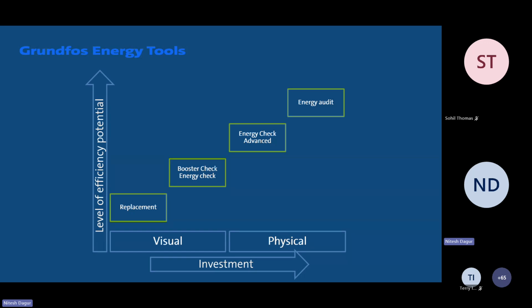Then comes energy check advanced. This is where we monitor a bit more parameters and we try to take the information from the building BMS. It can be done with a small sensor that is installed right at the site. And this, of course, is higher in investment because there's a sensor involved that we have to install. Then comes the energy audit, which is highest in the investment because we have to send our people out, install the equipment there, monitor the conditions, the flow, the energy consumption for up to 2 weeks, depending on the application again.